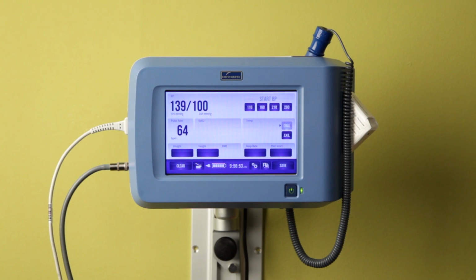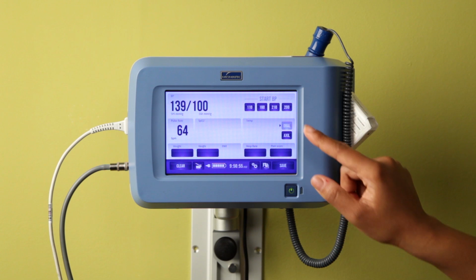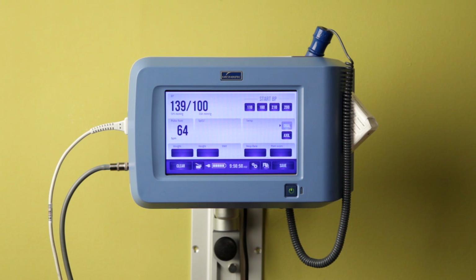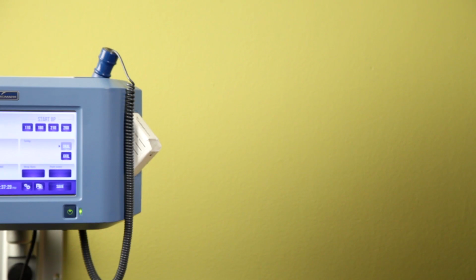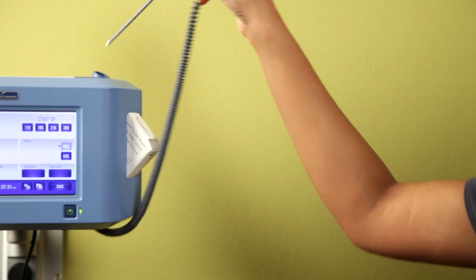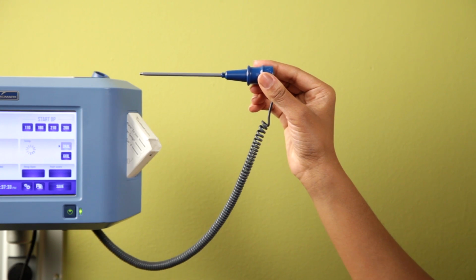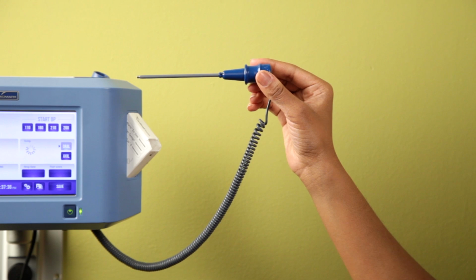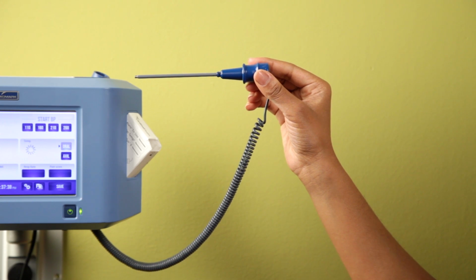To take a temperature, check the appropriate button in the main testing screen, oral for oral readings and axillary for axillary readings, and make sure that the button is light blue. Remove the probe from the probe well, grasping it in the top blue area between the thumb and index finger. Do not press down on the area where the cord comes out of the top.